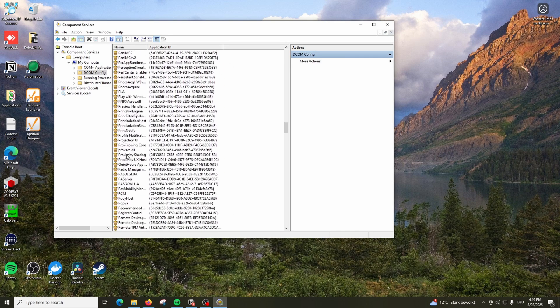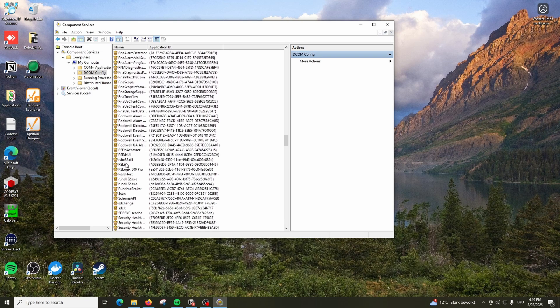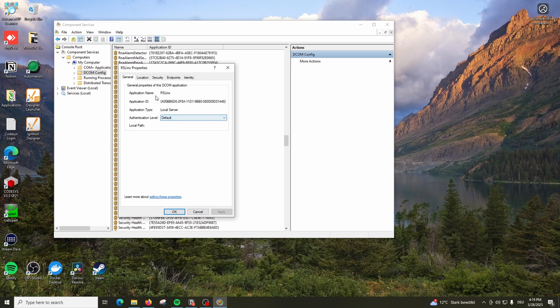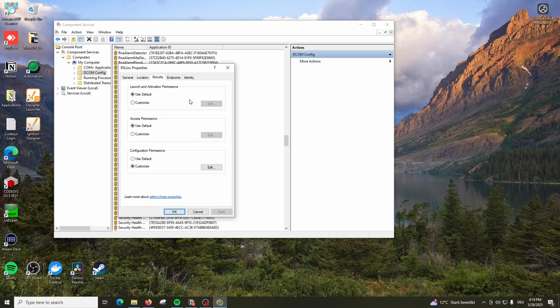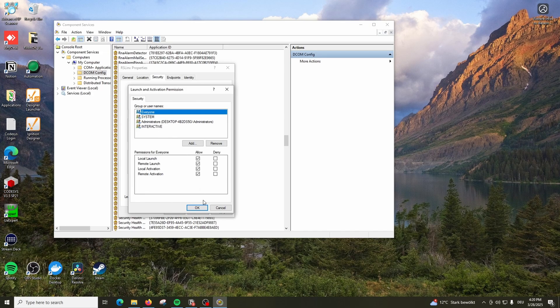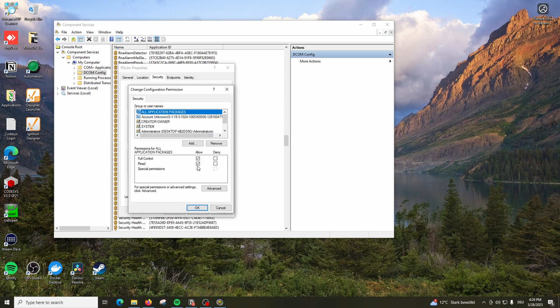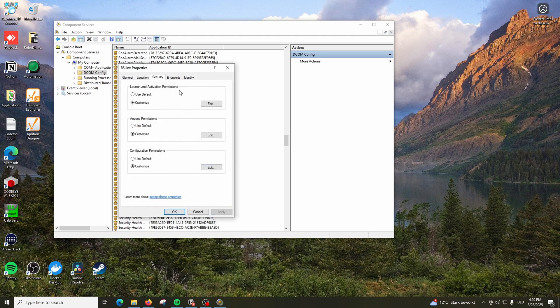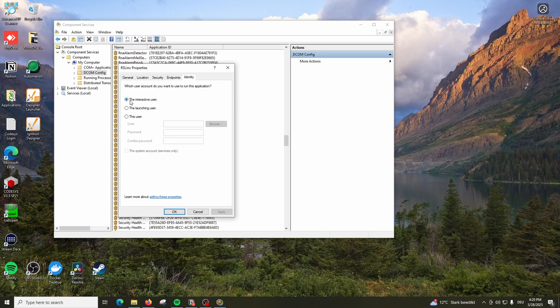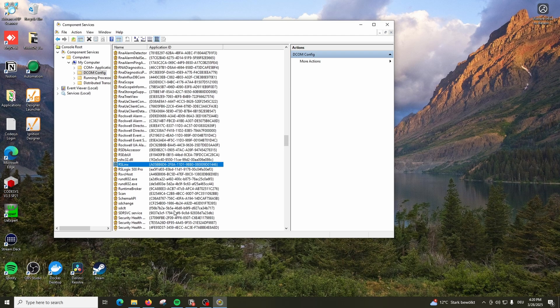Now search for RSLinx. Go to Properties. Authentication level and default location - you don't have to worry about the security, this is already set by default. Check Customize, click Edit, and make sure Everyone has everything checked. Also for Access Permission, Customize - everything is checked. Click Apply, then go to Identity. Make sure this is set to Interactive User. Click OK. These are all the settings you need to make things work.